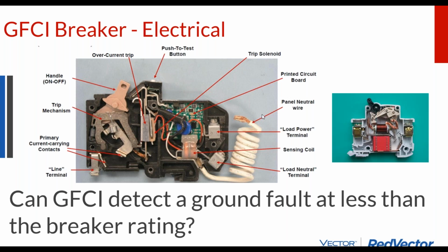Okay, but what about, say, an arc fault, where it's in line, but it's not as powerful as the entire appliance faulting to ground, where you just have a little light contact? What if the device that was ground faulting had two different power settings, one at full power and one at 1/3 power, and it was only ground faulting at 1/3 power? That would not be enough to open up the breaker, and it might not be enough to burn up any cables or cause any other errors, but it would still be occurring. So how do you detect these faults that are smaller than what the breaker is rated for?